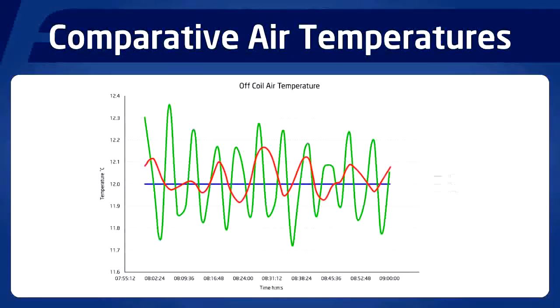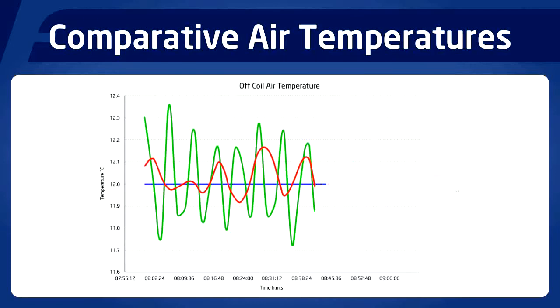If we zoom into an operating hour during one of the tests, we can see that the off-coil air temperature is controlled much more tightly by the pressure independent control valve compared to the two-port modulating valve. Both the amplitude and frequency of the temperature variation around the set point is higher when a two-port modulating valve is used with an authority of 0.1 or less.